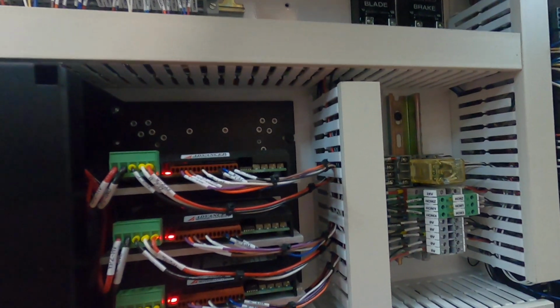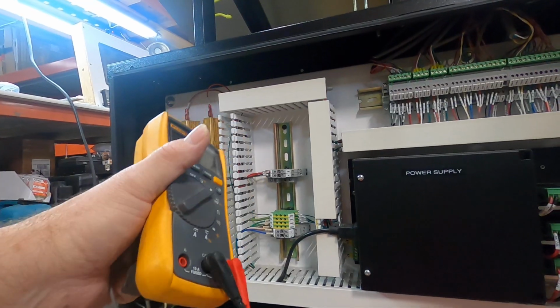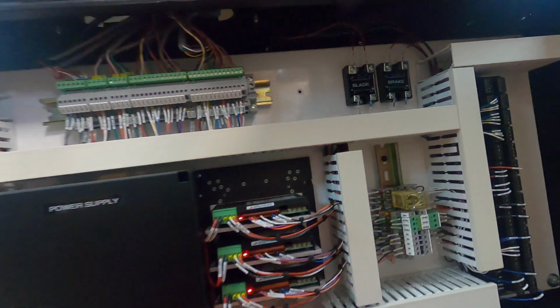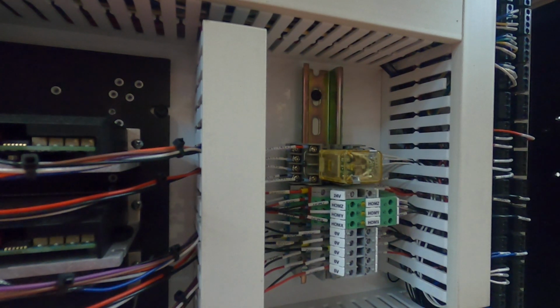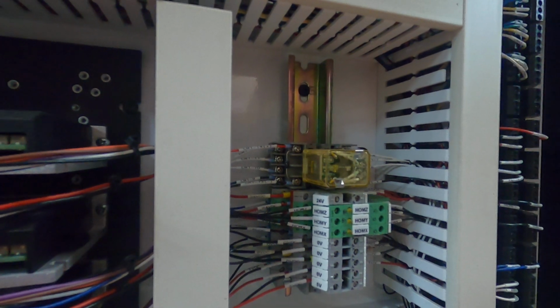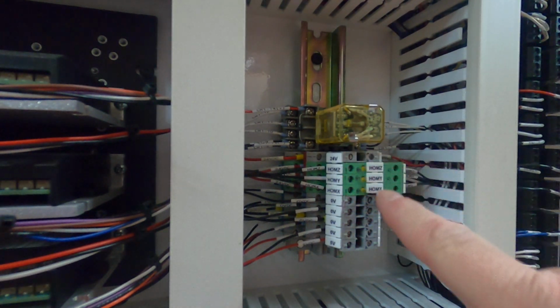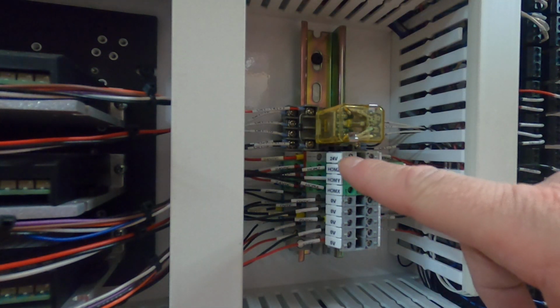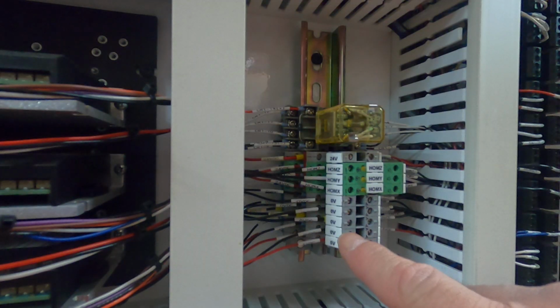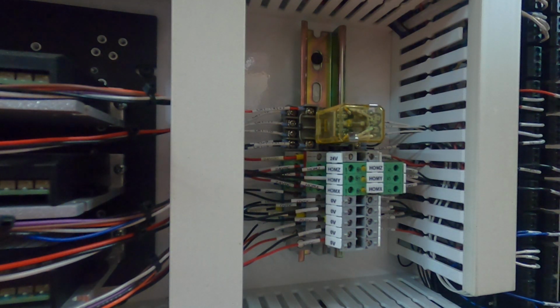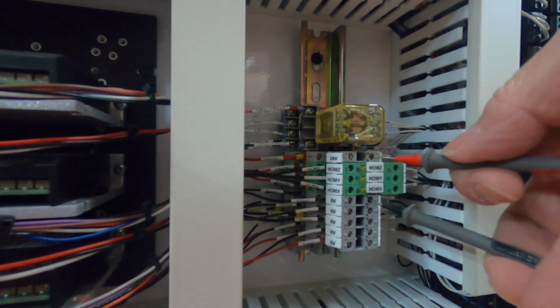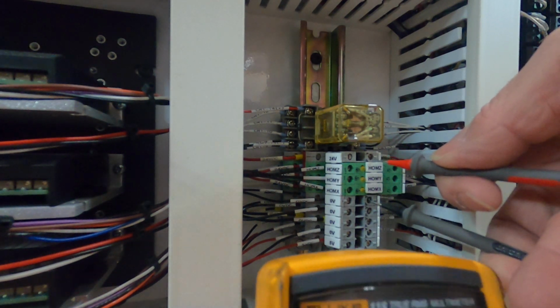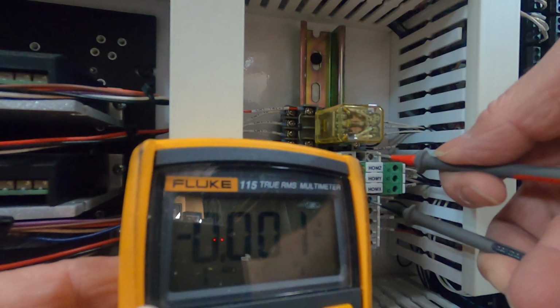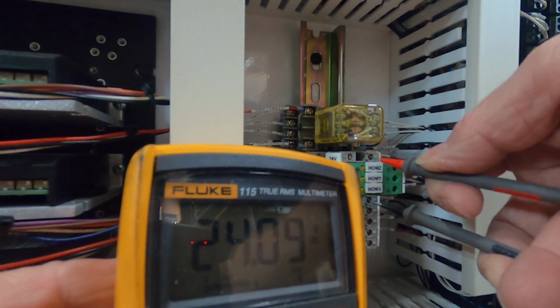Now, if I look over here, this is where I try to keep all the high voltage over here, the AC voltage, and try to keep all the DC voltage, low voltage over here, so we don't get any magnetic interference. So this area right here, this is a big power distribution for low voltage, and the top one says 24 volts, and all these say 0 volts, and this bottom one says 5 volts. So if I take my meter, we'll get it in the screen in a minute, but if I take my probe and I put it on the 0 volts, any screw on there, and then I put my probe here on the 24 volt screw, it reads 24 volts.